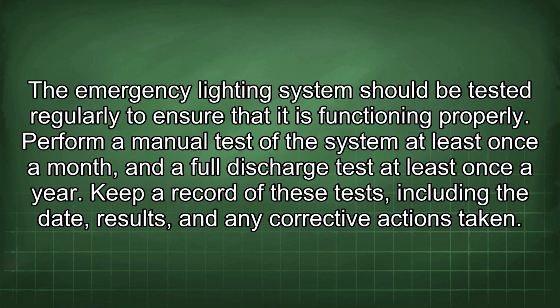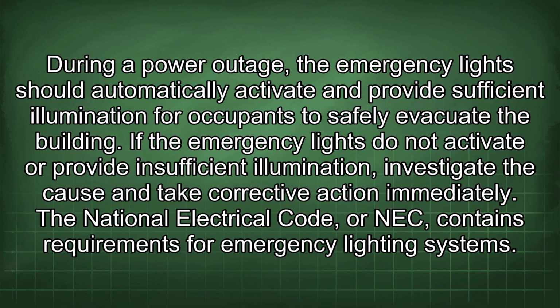The emergency lighting system should be tested regularly to ensure that it is functioning properly. Perform a manual test of the system at least once a month and a full discharge test at least once a year. Keep a record of these tests, including the date, results, and any corrective actions taken. During a power outage, the emergency light should automatically activate and provide sufficient illumination for occupants to safely evacuate the building. If the emergency lights do not activate or provide insufficient illumination, investigate the cause and take corrective action immediately.